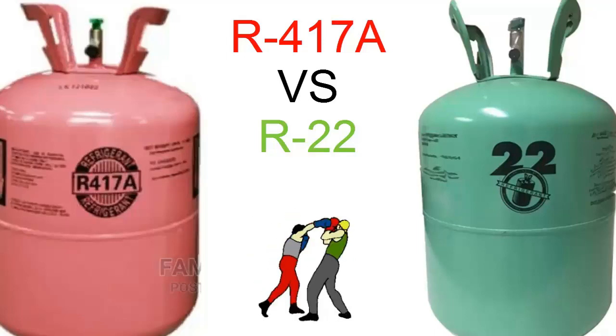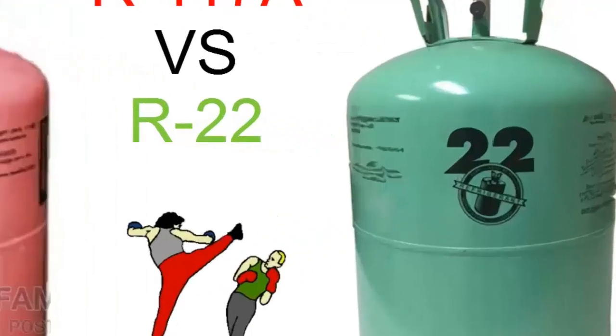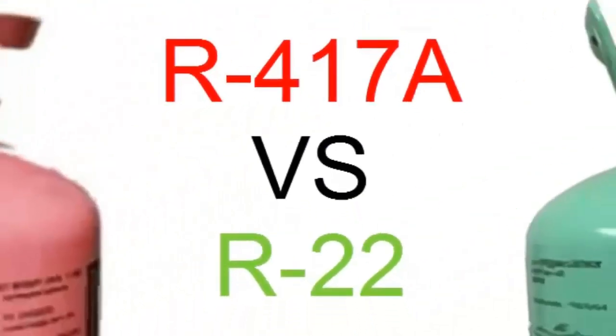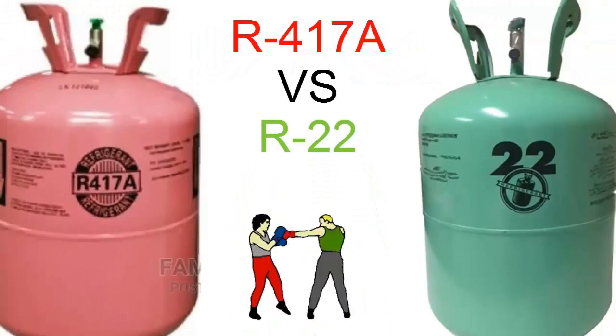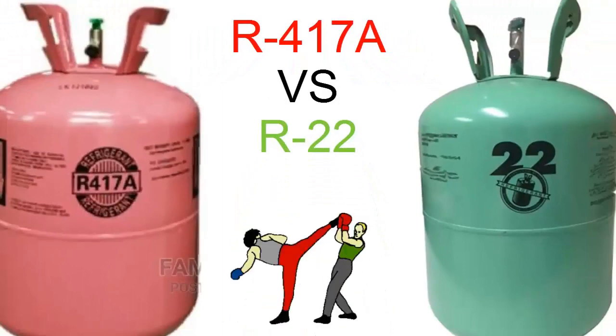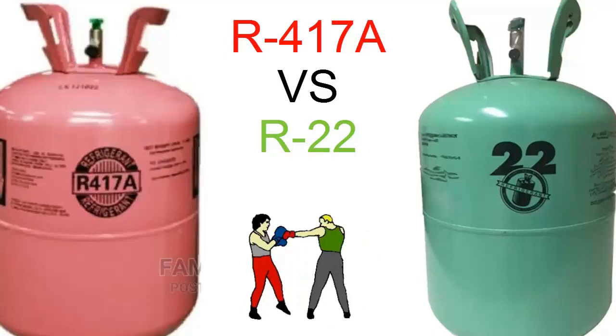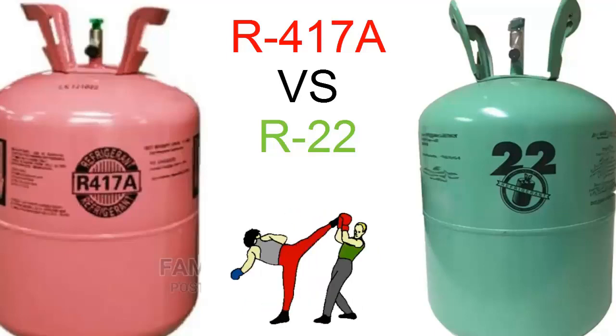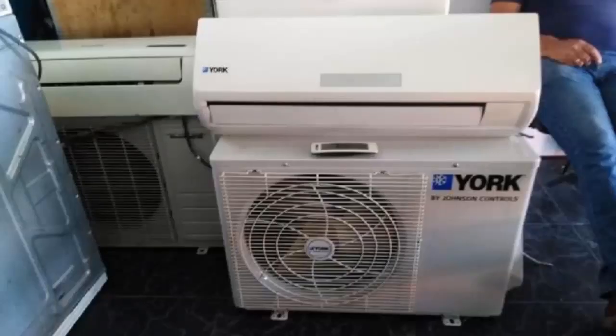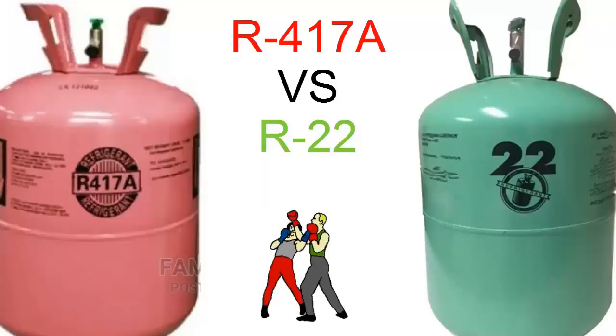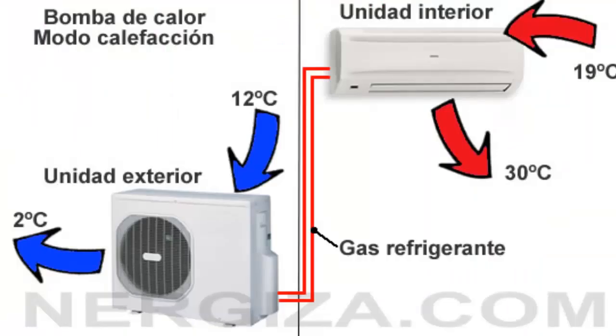Today, we will conduct a comparison between two refrigerant gases, R22, and its replacement, R417A. Before delving into the details, it's essential to highlight that R417A is a replacement gas for R22, specifically designed for medium and high temperature applications, such as refrigeration and air conditioning. It is also suitable for heat pump systems that previously used R22.